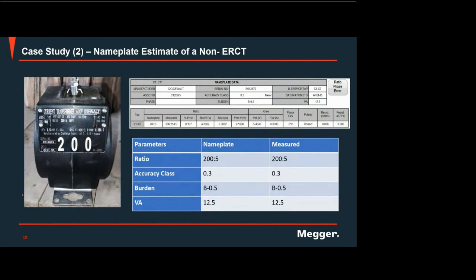So here, you got an ANSI CT, you got 0.3 B05 and 12.5 VA. This is the nameplate value. Now, the MBCT estimated that yes, it is 0.3, it is a B05, and it has a 12.5 VA. So the MBCT estimated the CT correctly. Nameplate versus measured are very identical.